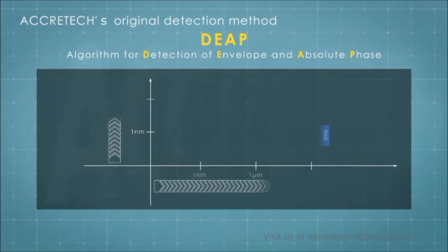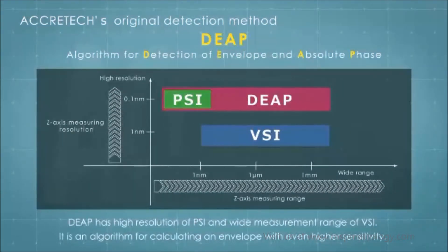Here we would like to show ACCRETECH's unique white light interference fringe peak detection method called DEAP, which is a special feature of the Optscope. DEAP stands for Algorithm for Detection of Envelope and Absolute Phase.